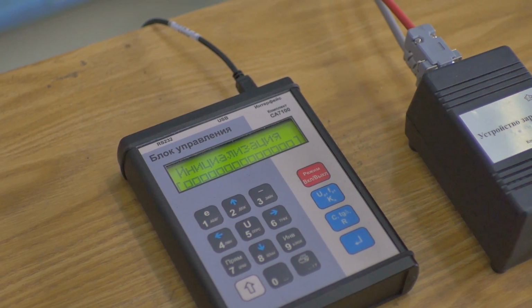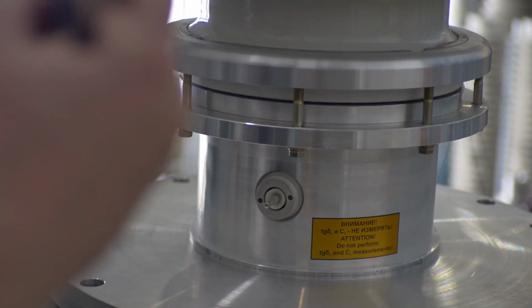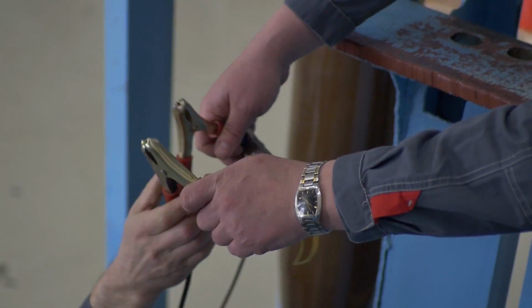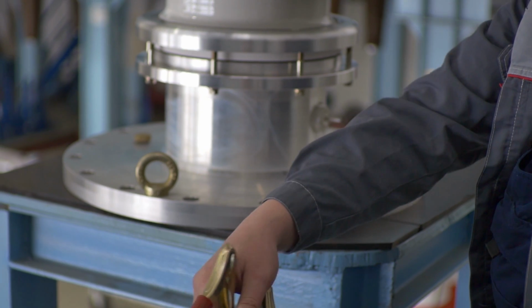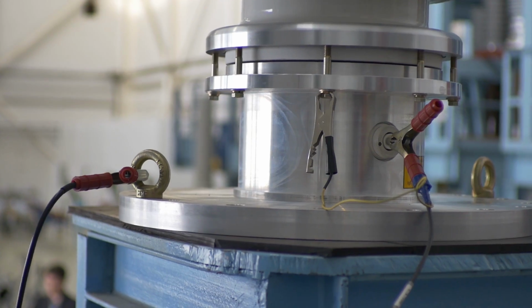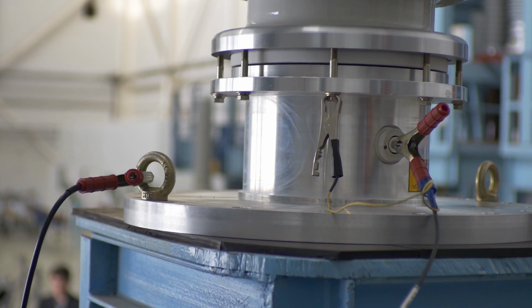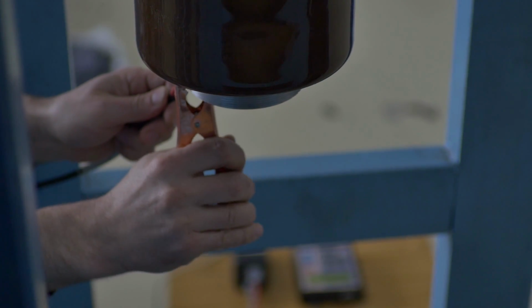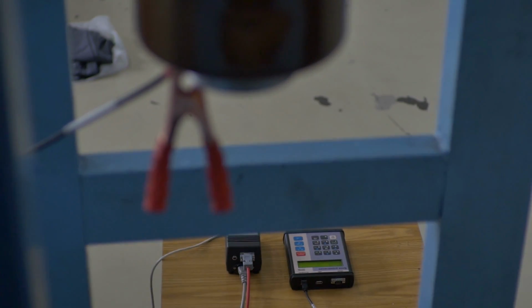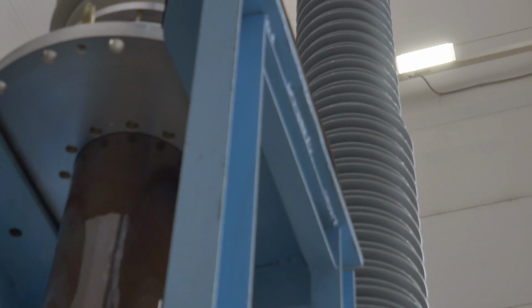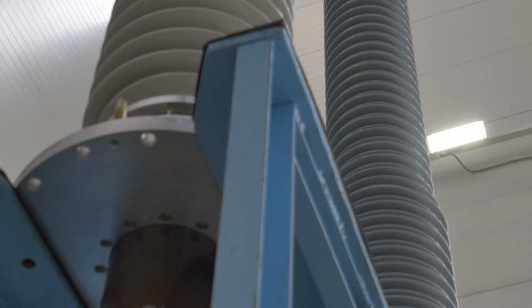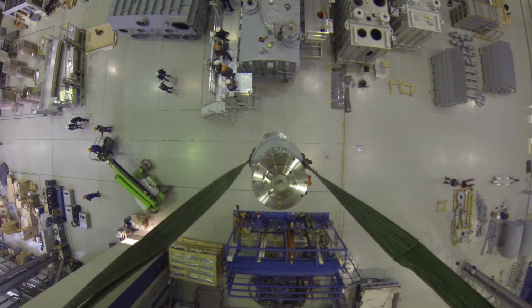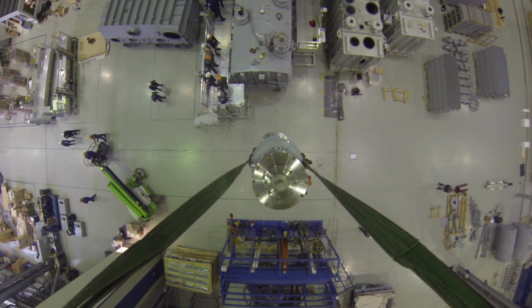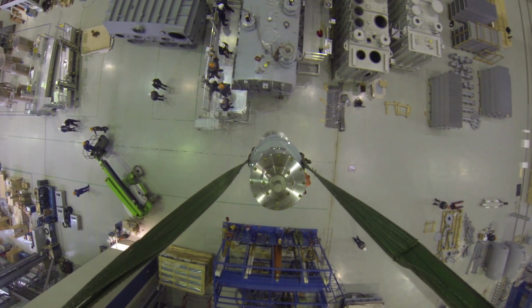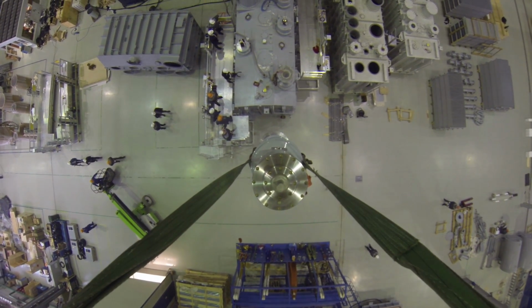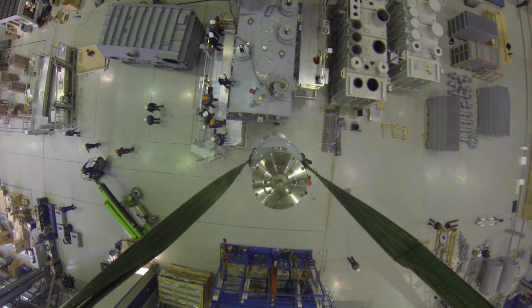However, should there be need to receive the main insulation's dielectric loss tangent measurement result approaching the one received at the plant, and the newly obtained results are higher, additional manipulations like the bushing's bottom side drying with a hot air blower and wiping with alcohol or anhydrous solvent are required. A thermal vacuum chamber of suitable size can also be used. Marginal acceptance growth of the main insulation makes 5% of the value received at operation commissioning of the bushing. The capacitance and loss angle tangent measurement values received at the acceptance tests are stated in the certificate of equipment.